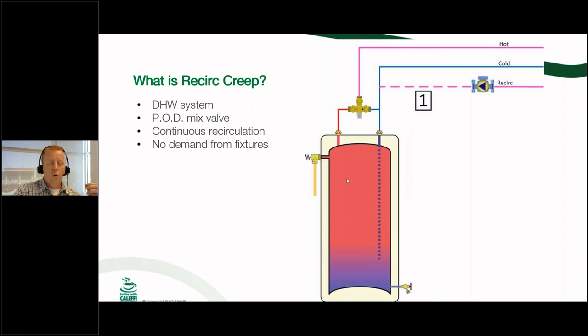Okay, so if you're storing your domestic hot water at 140, 150, 160, whatever you're storing it at, really, when you've got 115 coming back to the cold inlet and you want 120 coming out of here, you only need that tiny little bit of heat to bring that loop back up to temperature. And again, if this can't close down enough, you've got 150 or 160 degree water coming into there, and again, sooner or later, it's just going to start adding and piling on. And if you leave it go long enough, it can actually run up that distribution system in the recirc line all the way up to whatever you're storing that tank to. And again, whoever opens that first fixture, big surprise, hopefully no scalding, but then it's going to work perfectly the rest of the day, because again, you're going to have that continuous demand throughout the day, whether it be washing hands or showers or whatever the case may be.